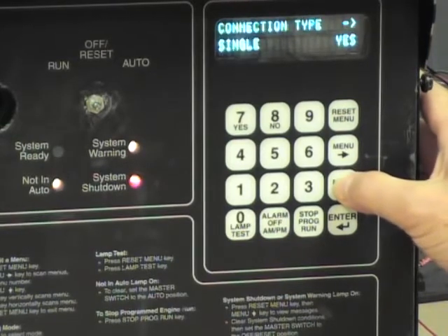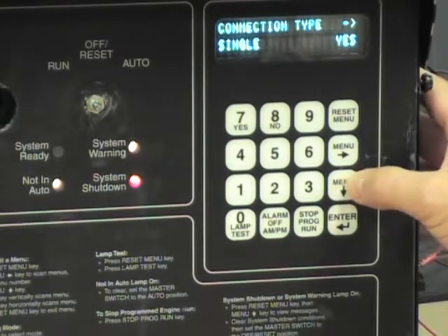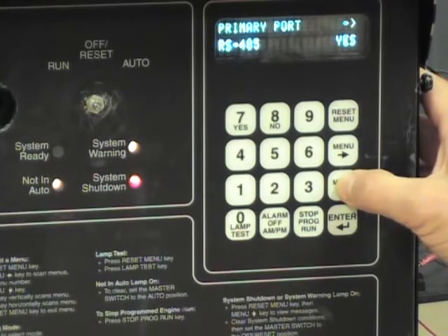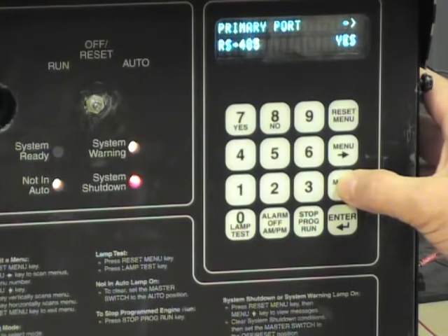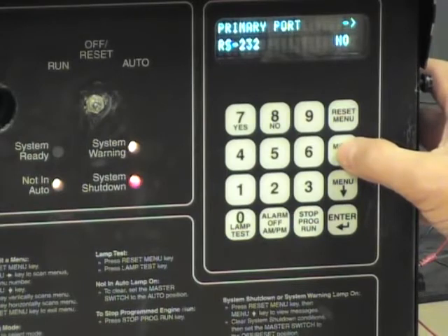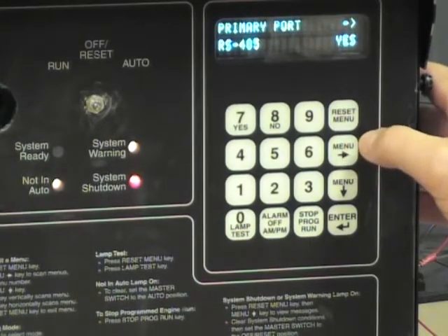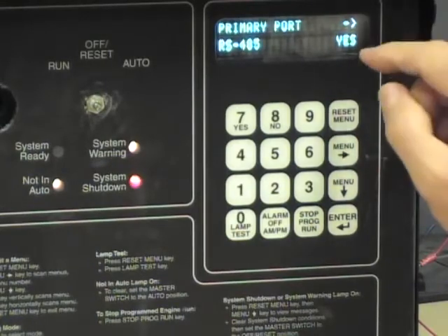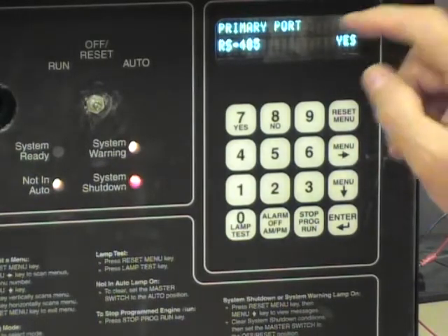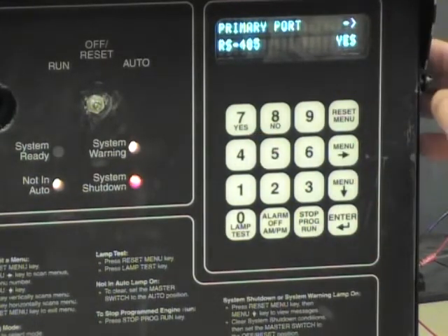Down arrow again. Connection type single — make sure it's yes. Down again. Primary port RS-485. Notice that if I use the right arrow key, we can toggle between RS-485 and 232. We'll stick with the 485. Should it not be yes, press the yes key to make it so.